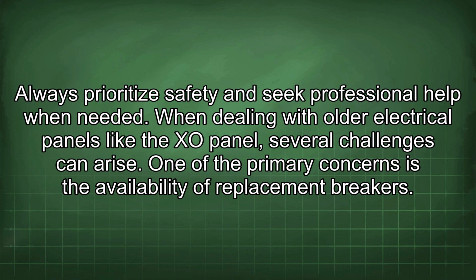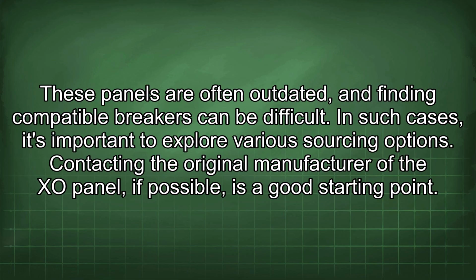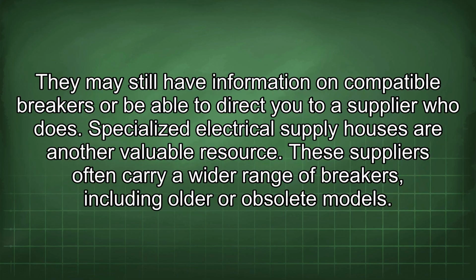When dealing with older electrical panels like the XO panel, several challenges can arise. One of the primary concerns is the availability of replacement breakers. These panels are often outdated, and finding compatible breakers can be difficult. In such cases, it's important to explore various sourcing options. Contacting the original manufacturer of the XO panel, if possible, is a good starting point. They may still have information on compatible breakers or be able to direct you to a supplier who does.